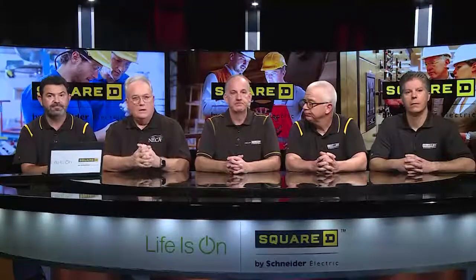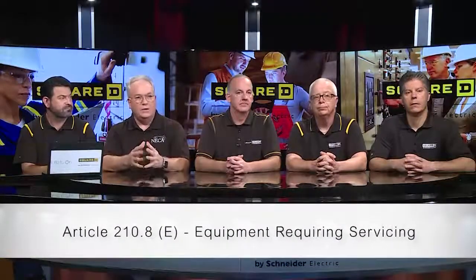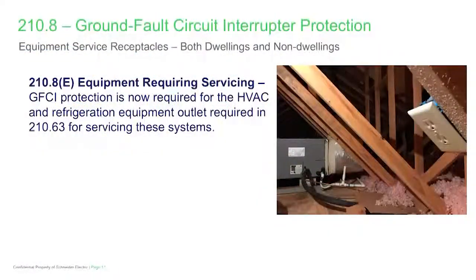When we move on to 210.8(E), it deals with equipment requiring servicing. This is your 210.63 application where the receptacle has to be provided for servicing HVAC equipment. The same change happened here that happened in residential — it really applies both indoor and outdoor. The GFCI requirement is certainly necessary in these locations for these types of operations to protect workers performing servicing of that type of equipment.